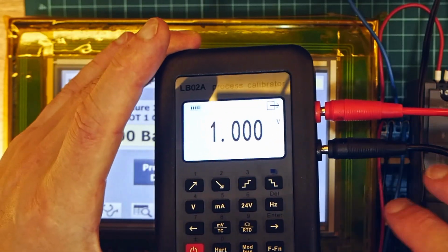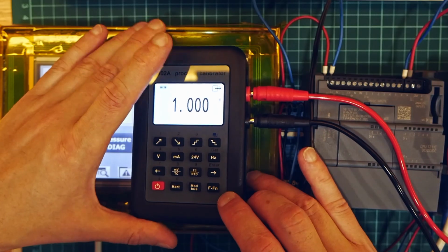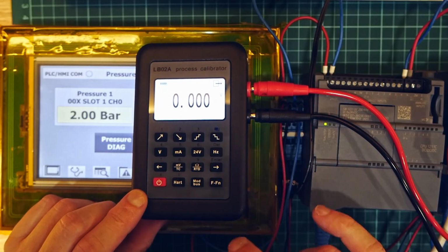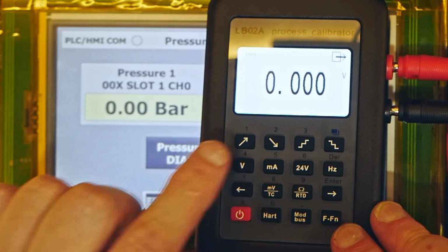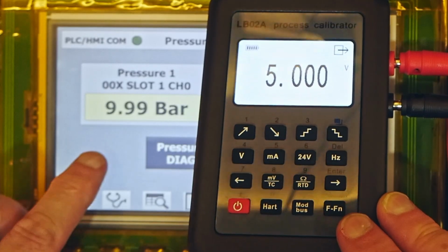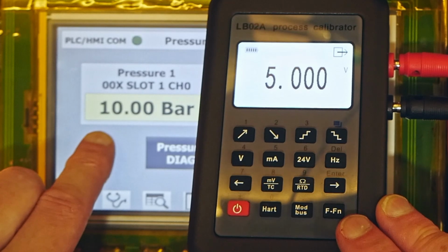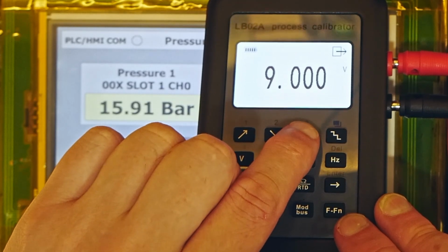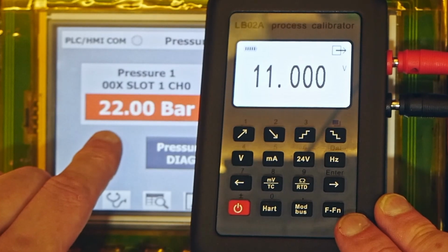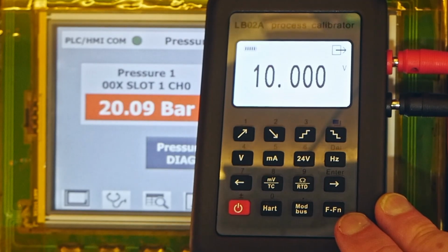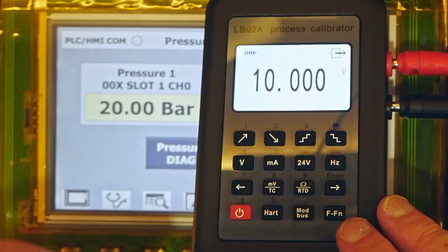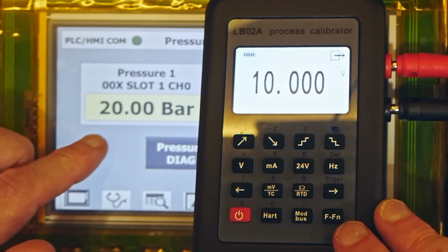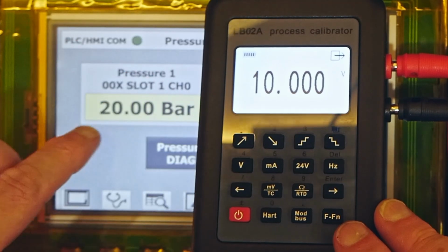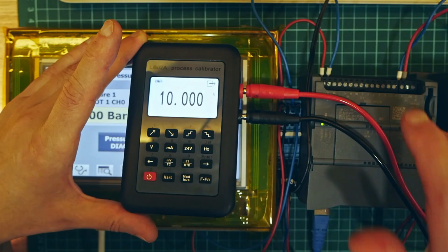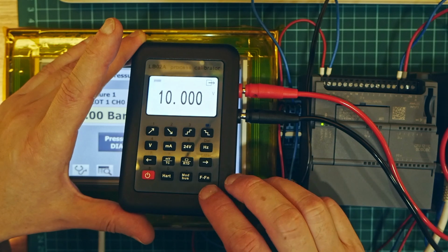So we hook up this process calibrator and we can simulate signal. Okay, let's say we simulate 0 volts, so our pressure is 0. We simulate 5 volts, so our pressure on HMI is 10 bars. Okay, let's go to 11. It goes to 22 bars. It goes outside the range. We can sweep all the range and check if this corresponds or not. Yes, because right now we are outputting 10 volts, we're getting 20 bars, so that means it's not our program. So with this device we can very quickly diagnose in which way to go and fix the issue.